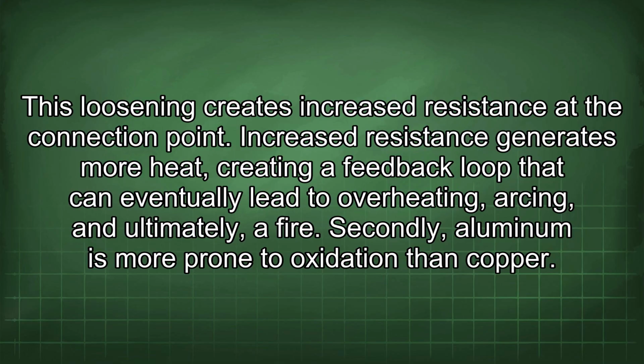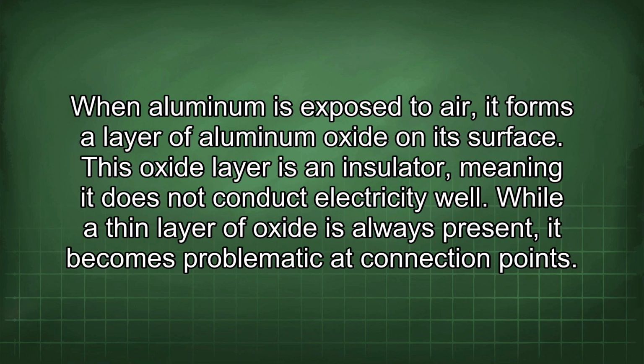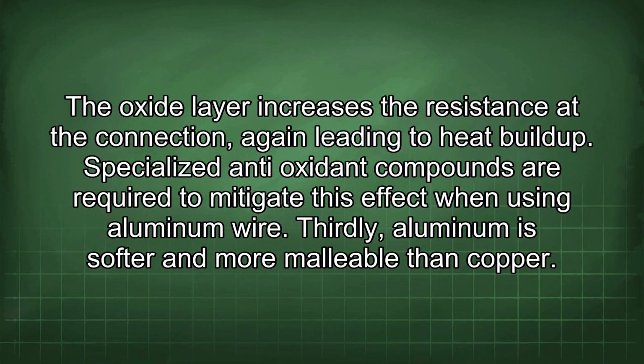Secondly, aluminum is more prone to oxidation than copper. When aluminum is exposed to air, it forms a layer of aluminum oxide on its surface. This oxide layer is an insulator, meaning it does not conduct electricity well. While a thin layer of oxide is always present, it becomes problematic at connection points. The oxide layer increases the resistance at the connection, again leading to heat buildup. Specialized antioxidant compounds are required to mitigate this effect when using aluminum wire.